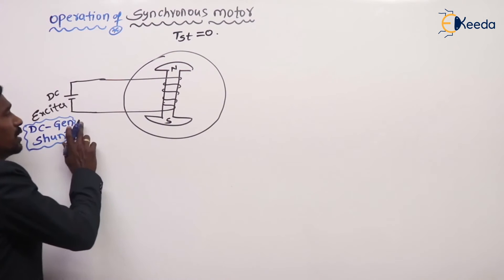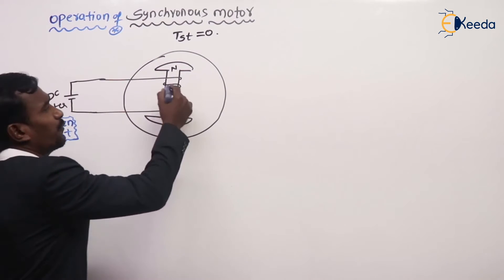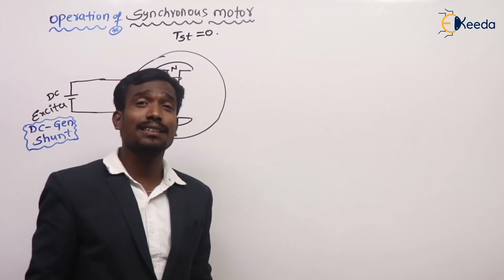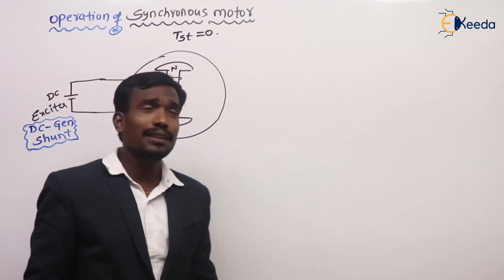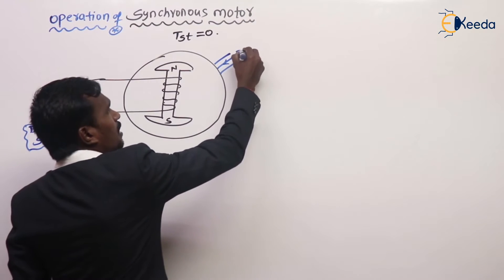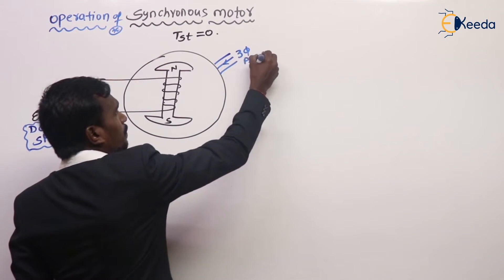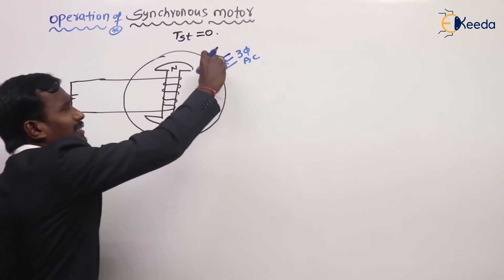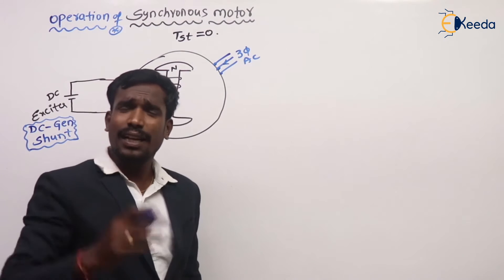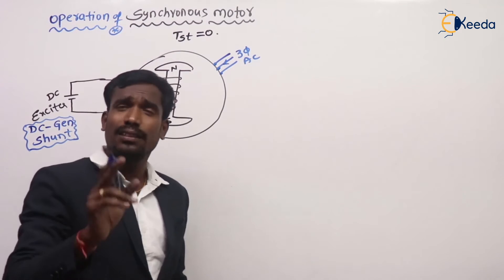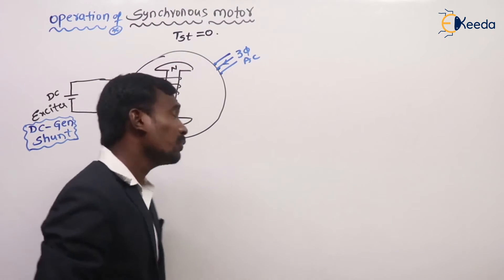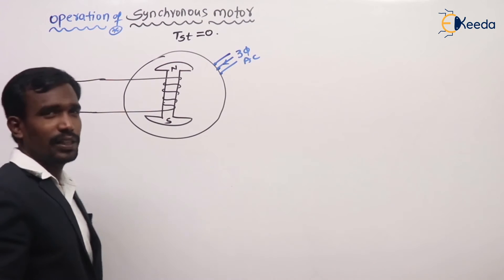The exciter develops power, which is then given to the field winding of the rotor. Some pilot generators — called pilot exciters — are also used. In that arrangement, three-phase AC supply is given to the armature, and some of that supply is given to a rectifier. The rectifier converts AC to DC, and that DC is given to the exciter. The exciter is essentially a DC shunt generator.